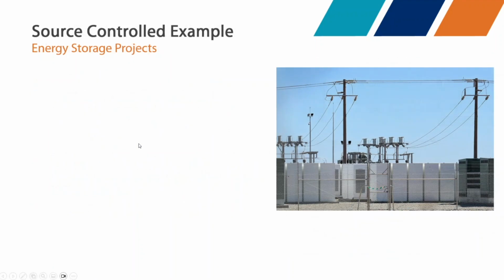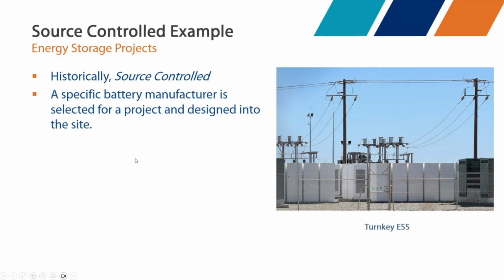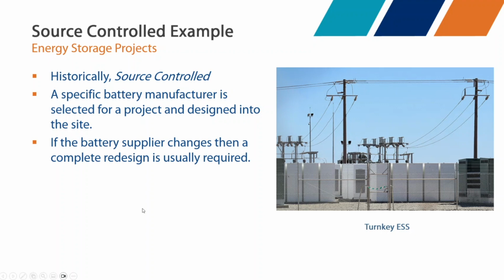Let's see how this has typically gone with energy storage projects. It's historically been source controlled, although there are examples of this changing. Usually a specific battery manufacturer is selected for a project and designed onto that site, maybe in a 20-foot container or some proprietary enclosure. If that energy storage supplier changes, you have a complete redesign of the site. The entire site needs to be redesigned for the new provider. Some providers might be similar, but they're not identical.